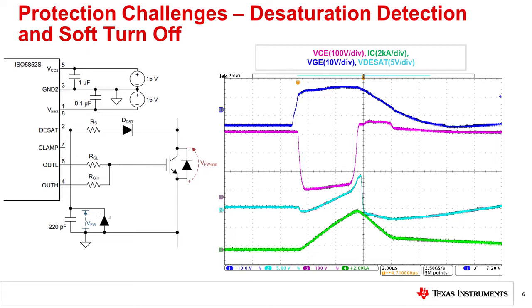The gate emitter voltage can be turned off quickly to prevent overcurrent damage, or slowly with a milliamp level constant current sink to prevent overvoltage damage from the high DiDT and parasitic lead inductance. Desat detection and soft turn-off are standard protection features offered for high reliability isolated IGBT gate drivers today.